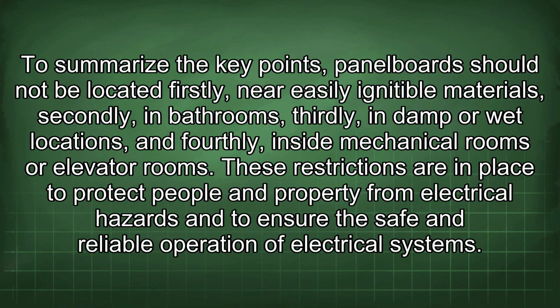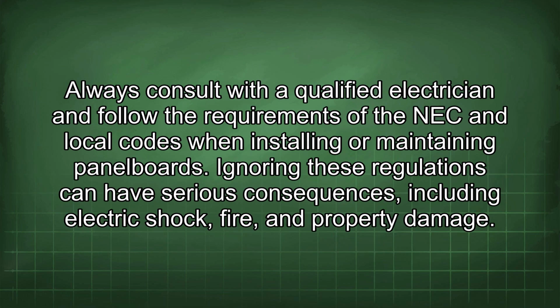To summarize the key points, panelboards should not be located, firstly, near easily ignitable materials, secondly, in bathrooms, thirdly, in damp or wet locations, and fourthly, inside mechanical rooms or elevator rooms. These restrictions are in place to protect people and property from electrical hazards and to ensure the safe and reliable operation of electrical systems. Always consult with a qualified electrician and follow the requirements of the NEC and local codes when installing or maintaining panelboards. Ignoring these regulations can have serious consequences, including electric shock, fire, and property damage.